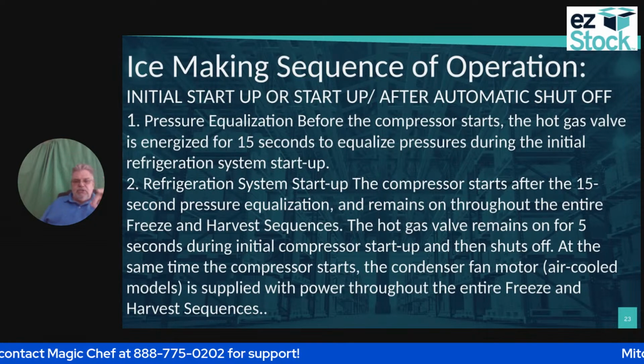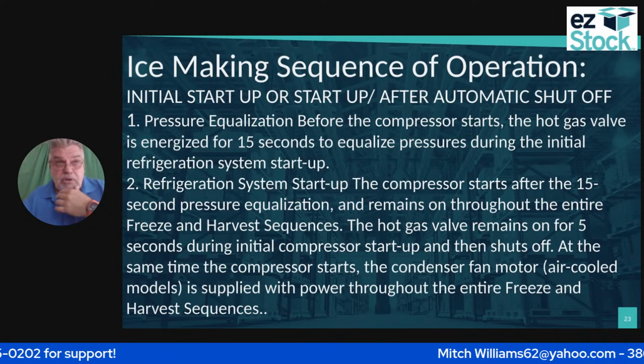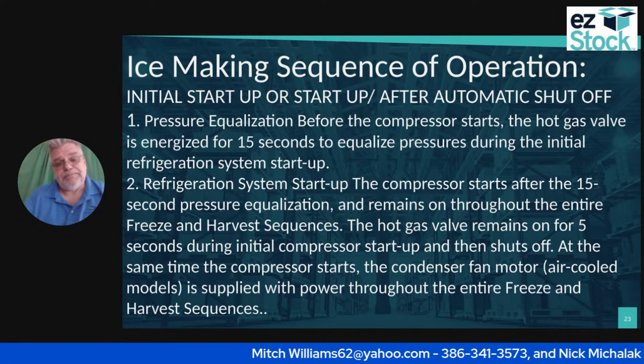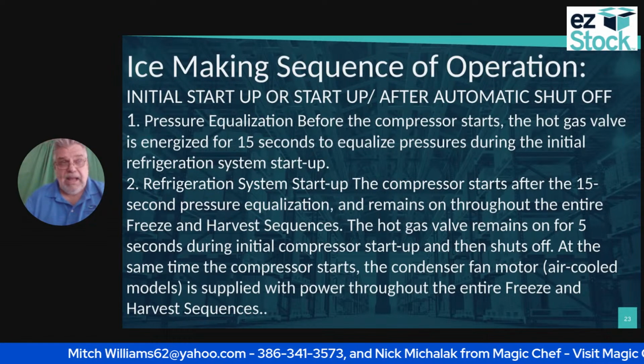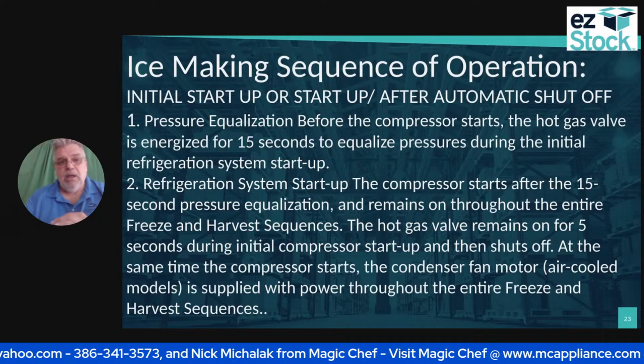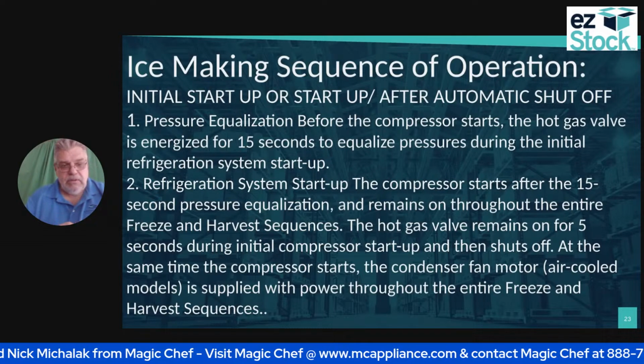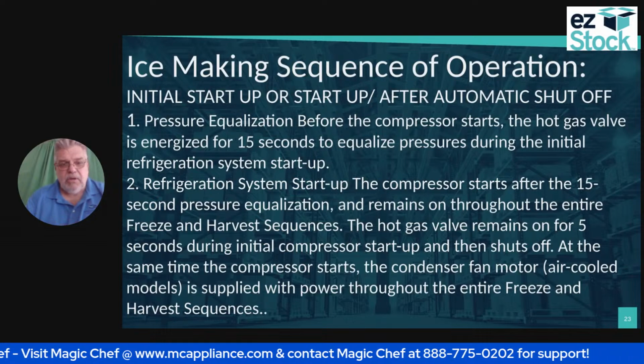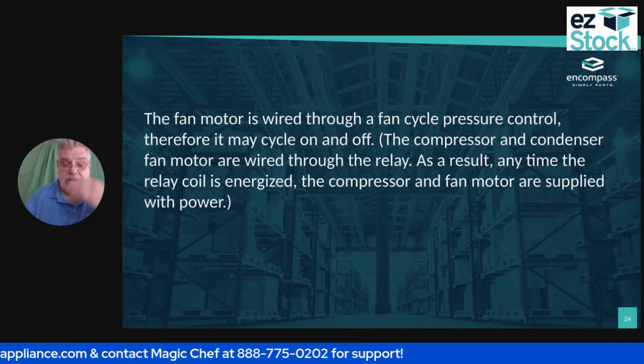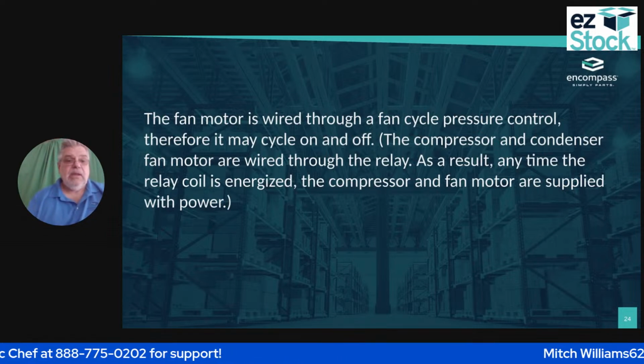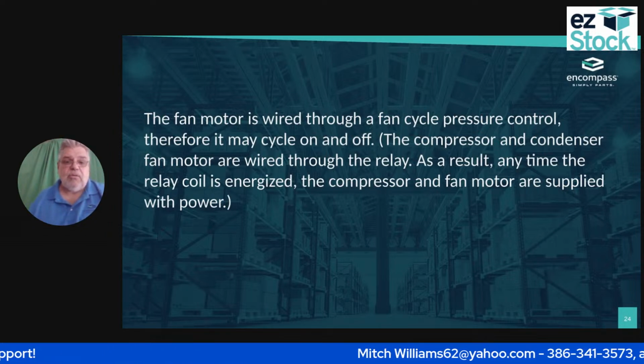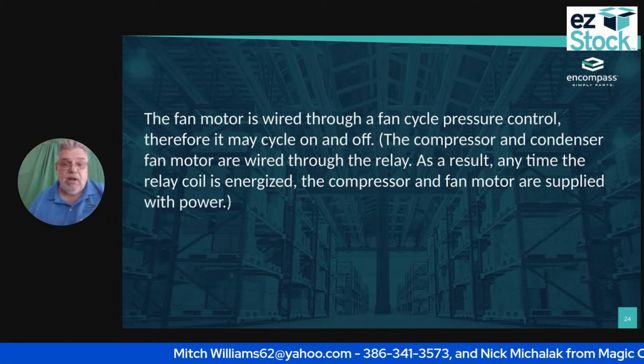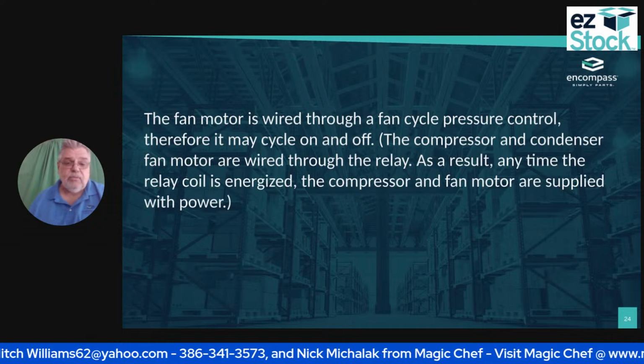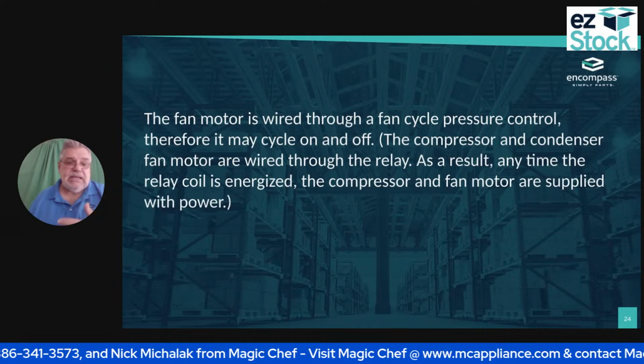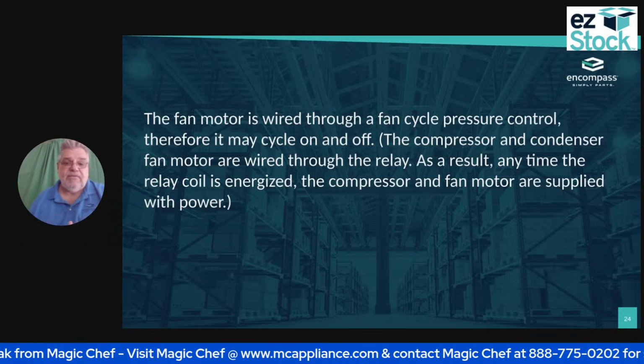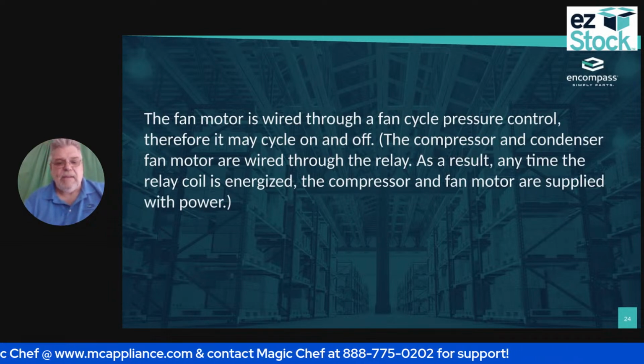Okay, so as you can probably guess, this is another reason that I have to make sure that I've got the proper clearances for my airflow, because it would put such a strain on that condenser fan motor that I end up replacing the fan motor because it's gone out prematurely. Okay, the fan motor is wired through a fan cycle pressure control. Therefore, it may cycle on and off. The compressor and the condenser fan motor are wired through a relay. As a result, anytime the relay coil is energized, the compressor and the fan motor are supplied with power.